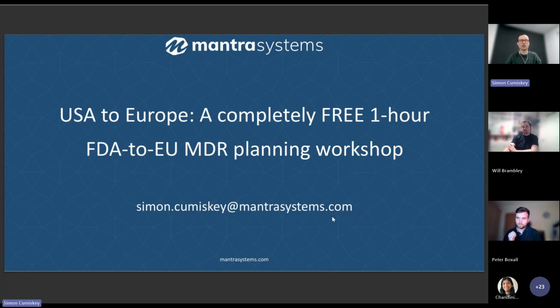A little bit less, well, it should have the same focus on the manufacturing processes, but they also want you to have considered the risks associated with normal use of the device when the device is not in failure mode, but also the risks that exist with the intended user. And so our approach to risk management as a company is we use a preliminary hazards analysis, and that does complement FMEAs in some way. But yeah, big gap for me.